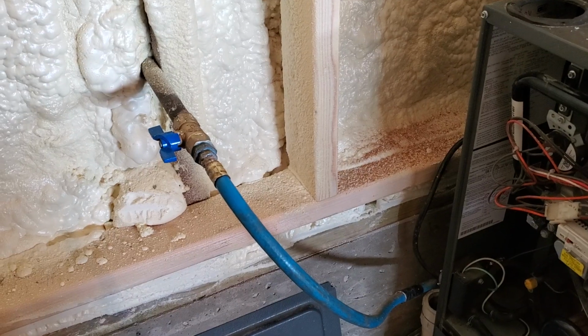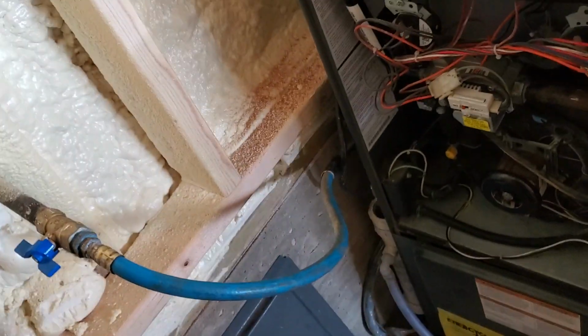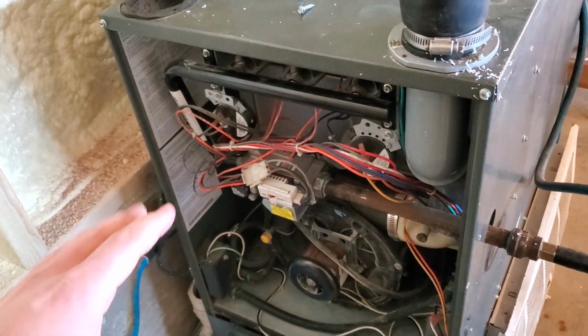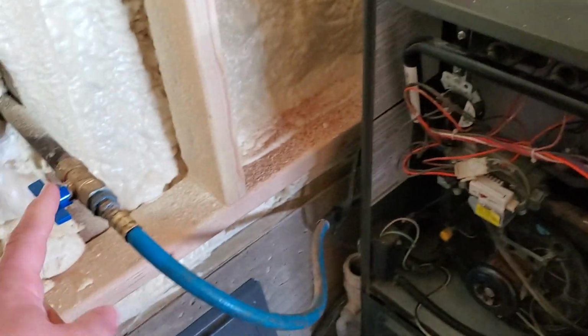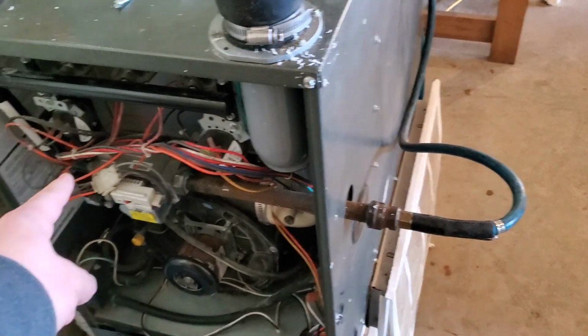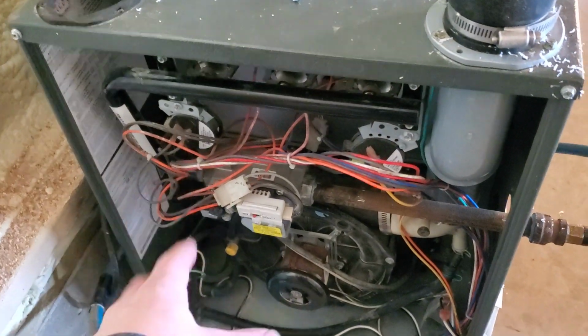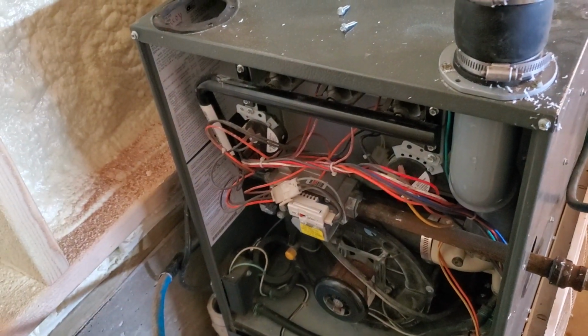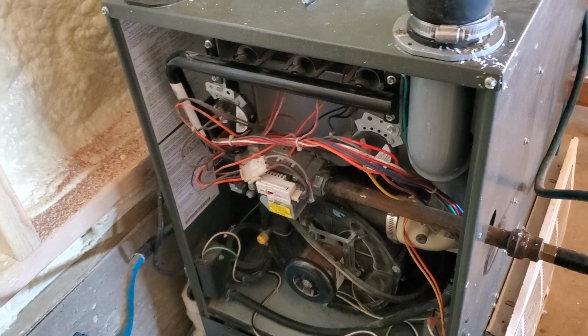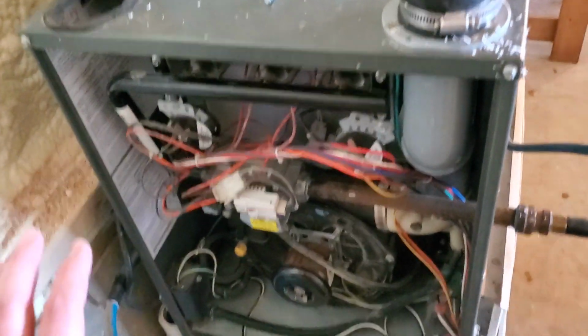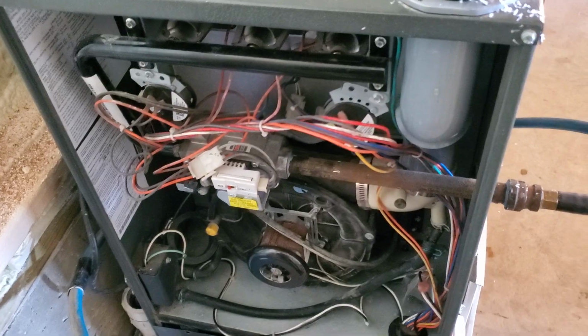Now for our gas line, in this instance, we actually had a flexible hose here. It's an air hose that we're using temporarily for the furnace because we originally had the furnace over on that corner of this building, and that's convenient, gives you some flexibility. The furnace needs approximately 11 inches of water column for the pressure coming into your gas valve. So you want to make sure that you hook something up that is the correct pressure feeding your furnace. And then obviously go ahead and check and make sure that you have no leaks on any of your fittings, and be 100% sure that you're good to go before you fire it up.